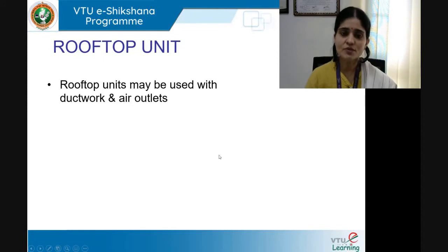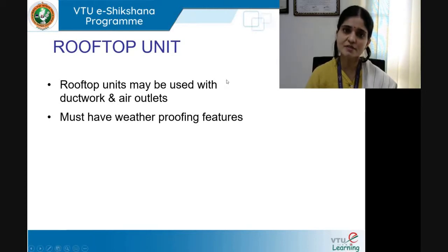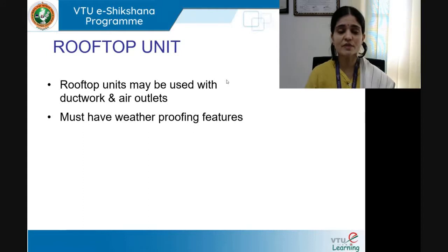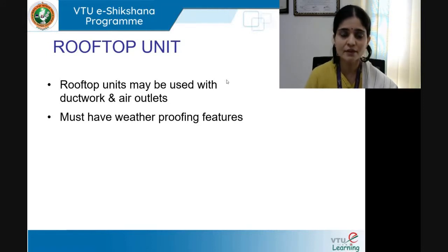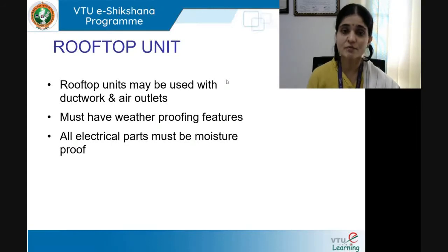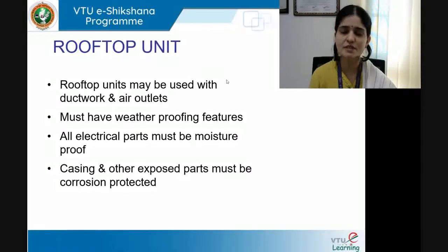Rooftop units may be used with ductwork and air outlets to transport air from one point to another. Since the equipment is placed on the rooftop and exposed to the elements, they must have weatherproofing features — protection from rain, harsh sun, wind, thunder, and lightning. All electrical parts must be moisture-proof to avoid mishaps, and the casing and other exposed parts must be corrosion-protected due to outdoor rain and humidity exposure.